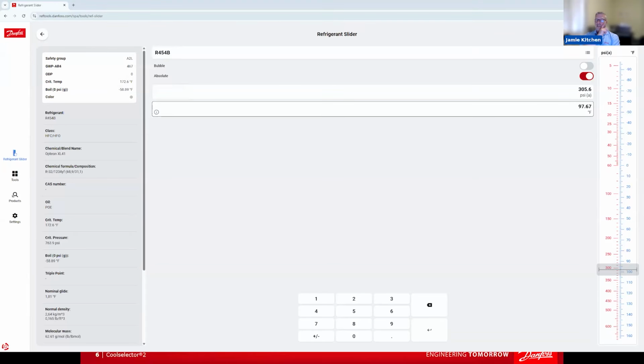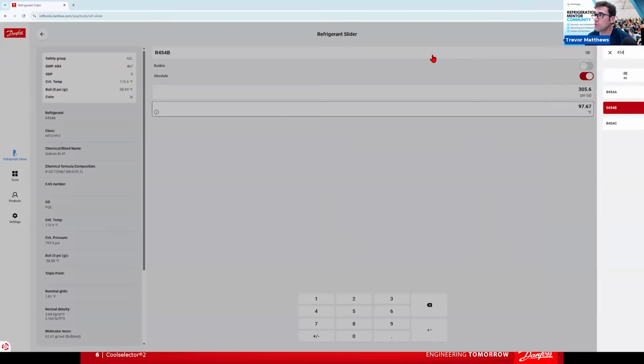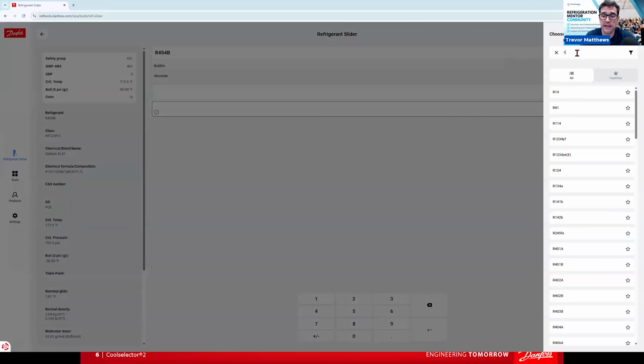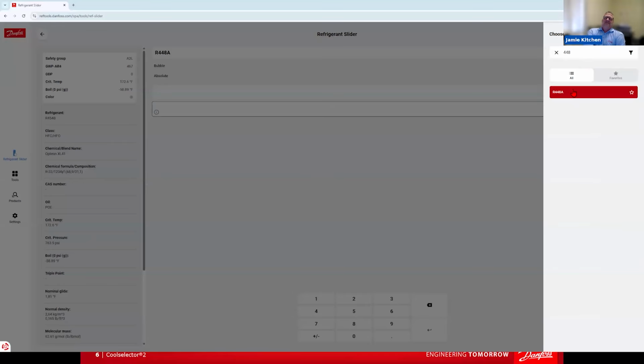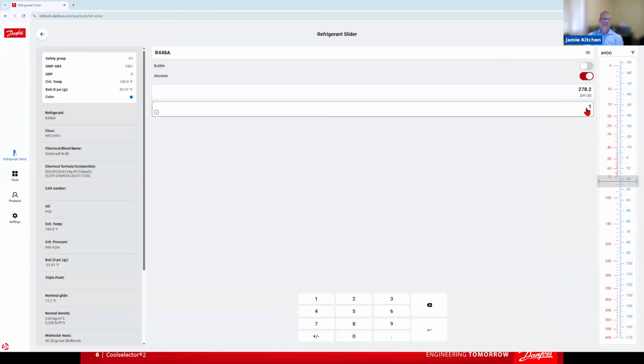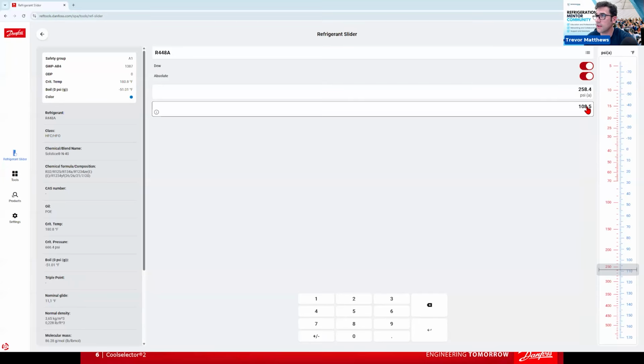Now, remember, you use your dew point for checking superheat. You use your bubble point for checking subcooling. I don't expect anybody to remember that, right? That's okay. But that's important because when we go to a refrigerant, say like 448 now. Oof, not my favorite refrigerant, but we have it. Well, watch this. You got 100 in absolute, and then you have a bubble point, and then it's 108 in dew. And that's enough to make a difference.